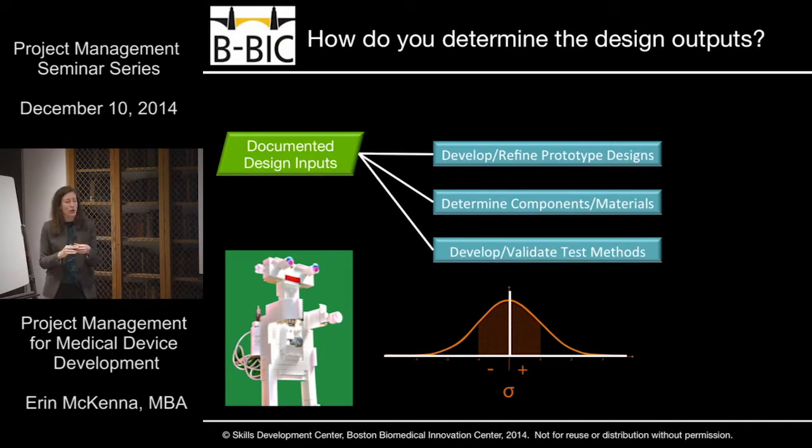You're going to be looking to try to understand at this point what's the overall space that your design could exist in. So for instance, I've talked about a catheter length of 120 centimeters. Could the product still work at 119, 118? Where's that drop off before it gets to the point that putting the product in would just not achieve its goal? So you're going to be using a lot of, I don't know how many of you are familiar with Design for Six Sigma tools, designs of experiments.